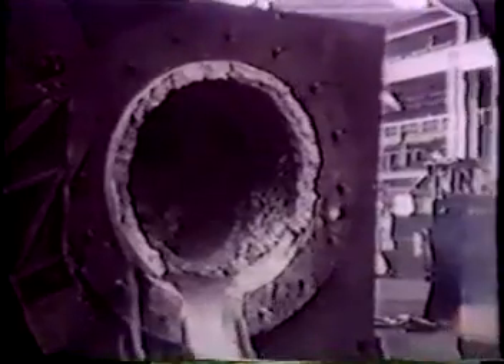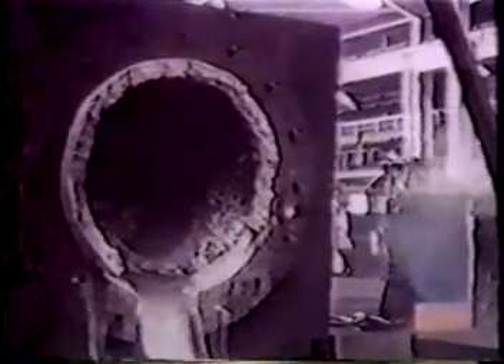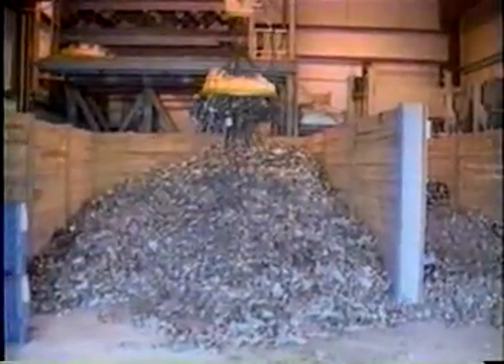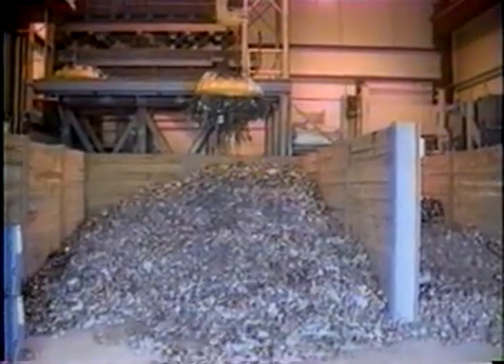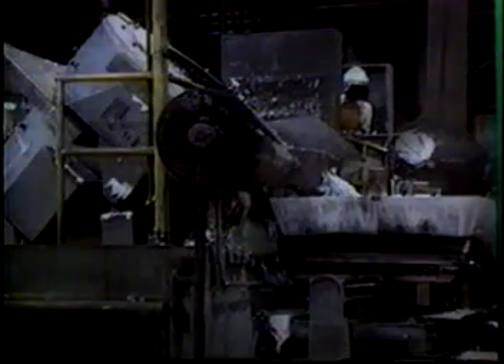Once the bridge has been melted away, the furnace should be poured empty as soon as possible so the lining can be examined for any signs of damage. If there is any doubt about the integrity of the lining, replace it. The chance of a bridging situation occurring can be minimized by using proper charge material and by making sure that different sizes of charge material are added correctly. It is vital that every furnace operator be able to recognize and react correctly to a bridging situation in his furnace. His life and the lives of his co-workers may depend on it.